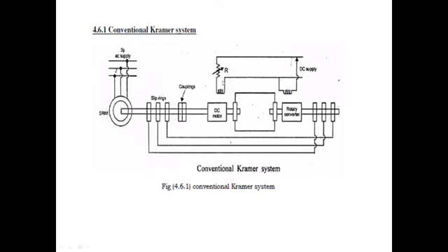This method of speed control is used in large power applications where the variation of speed over a wide range involves a large amount of slip power. The power absorbed by the source, via the magnitude and the sign of PR, can be controlled by controlling the magnitude and phase. A positive PR will reduce PM, and therefore the motor will run at a lower speed at the same torque. When PR is made equal to PG, then PM and consequently speed will be 0. Thus variation of PR from 0 to PG will allow speed control from synchronous to 0 speed.